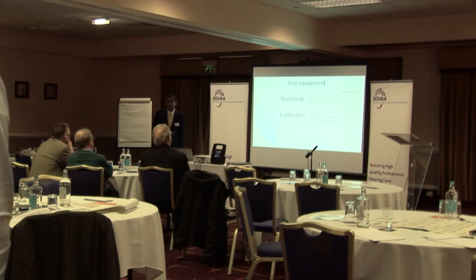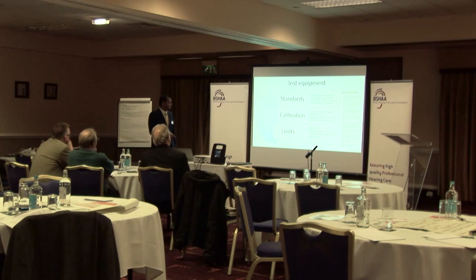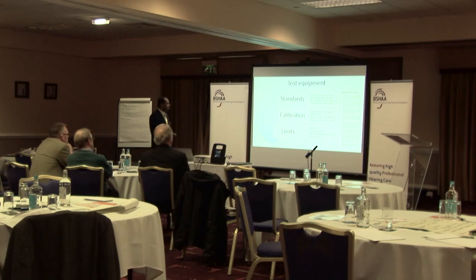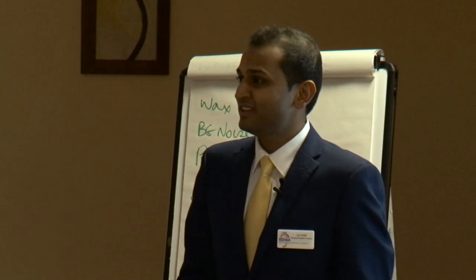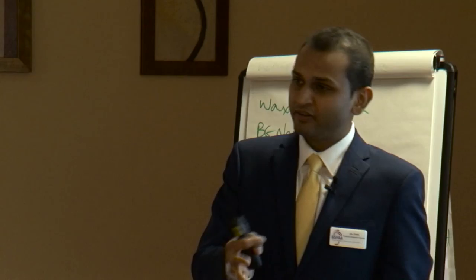Most of the content on test equipment comes from the BSA protocol, which refers to standards around calibration requirements. There are different stages of calibration you have to do every day. If you haven't recorded that you've done stage A and stage B, then you haven't done it. What I do is: whenever I open my audiometer, I'll do a hearing test on myself — and that's recorded on that date. I know I've done the stage A calibration test. I recommend you either have a sheet where you record it every day or every time you've done it.